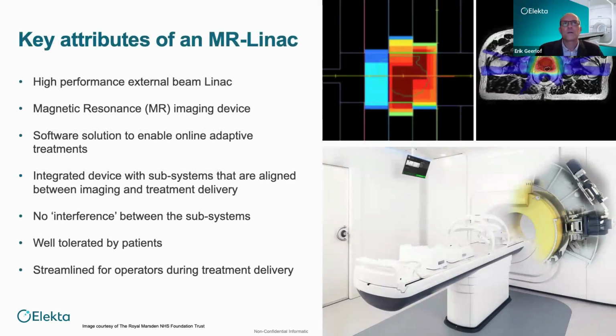First of all, we are talking about a high performance external beam linear accelerator. And secondly, we have a magnetic resonance image device. Here in the picture on the right side, you can see in yellow in the middle basically the MRI scanner. And around the MRI scanner, we have a slip ring device on which the linear accelerator components are mounted. So everything that's outside of the scanner is basically what makes the linear accelerator.